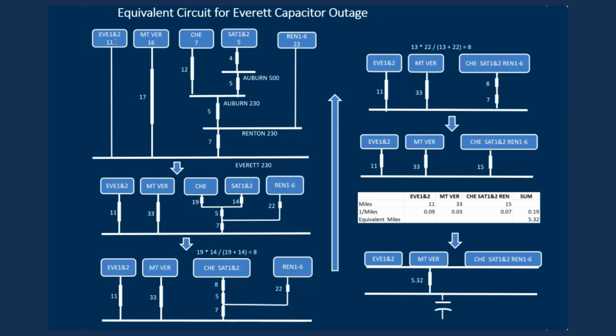In this step, we're simply taking the equivalent distance of the generator step-up transformer and making it explicit on a path. Or we're combining the generator step-up transformer with the path distance. So here we have 16 plus 17 gives us the 33. For Chehalis, the transformer is 7, the path is 12, it becomes 19.